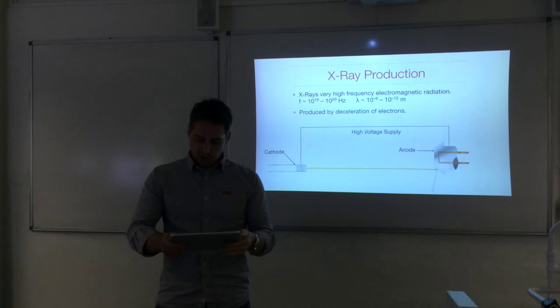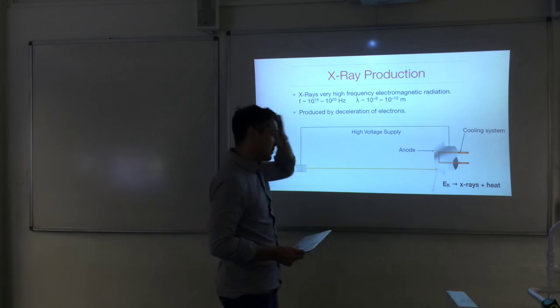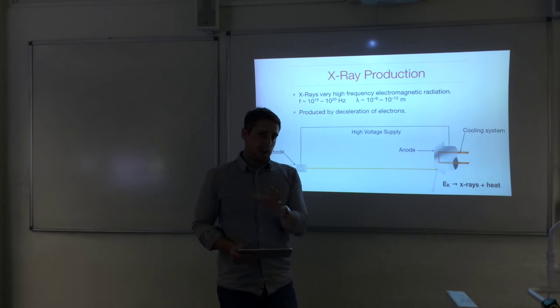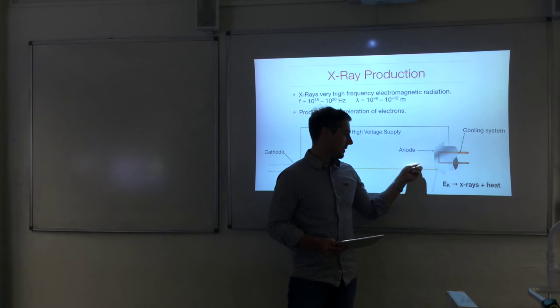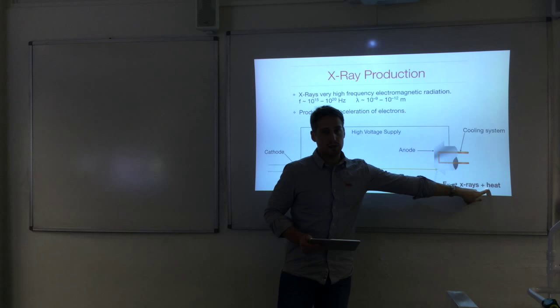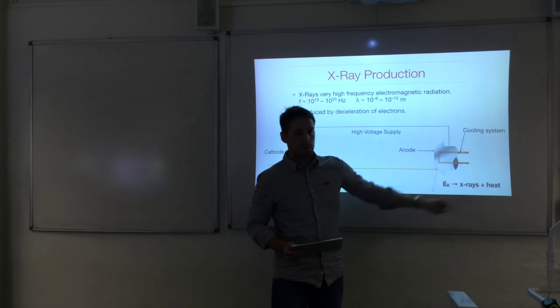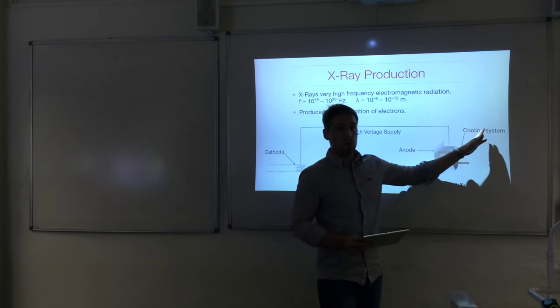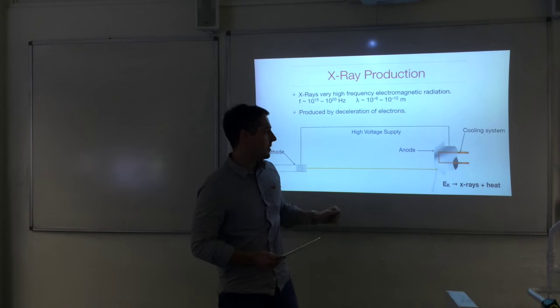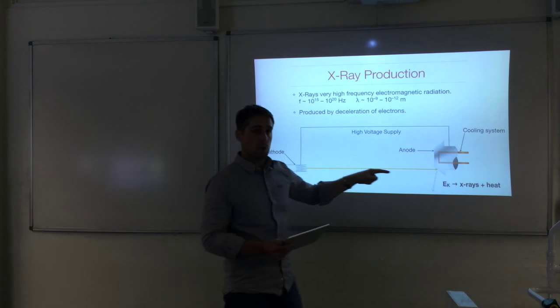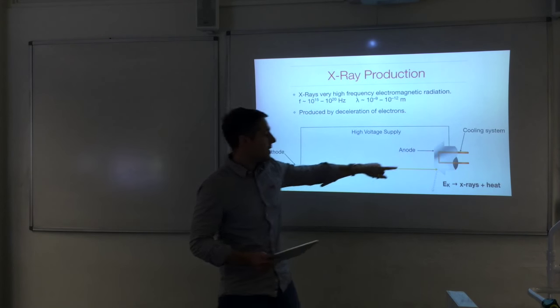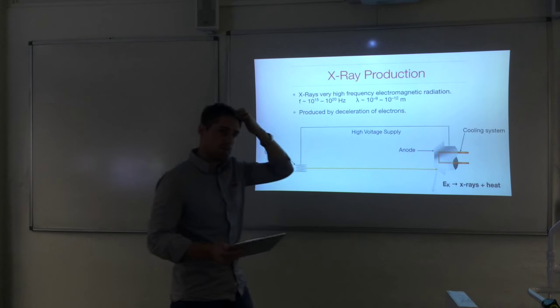There is an energy conversion at the anode: the electron kinetic energy is converted into x-rays and heat. Most of the energy — about 99% — is converted into heat, and only 1% goes into forming x-ray photons. Hence the need for methods to keep the anode cool: a cooling system pumps coolant through the anode, and it is often rotated so that heat input is distributed throughout the metal rather than concentrated in one small region.